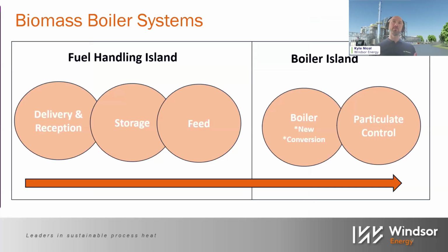They can be split into two islands. So you've got a fuel handling island, and then you've got a boiler island. The fuel handling island is how it gets delivered. So you get a truck, and there's a reception area, and then there's fuel storage, and then there's a feed which goes to the boiler. And the boiler island, you'll have a boiler which could be a new dedicated biomass boiler, or it could be converted from a coal boiler. And then there's usually particulate control on the back end of that.